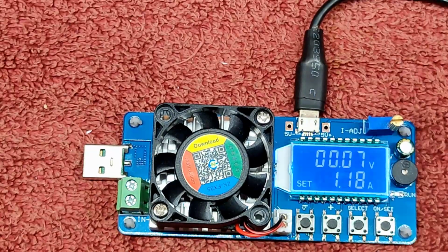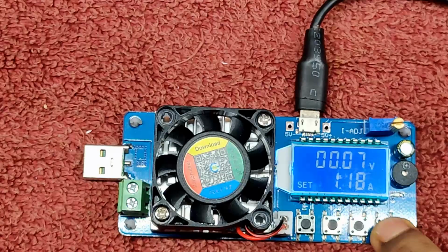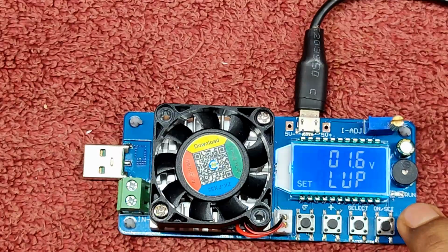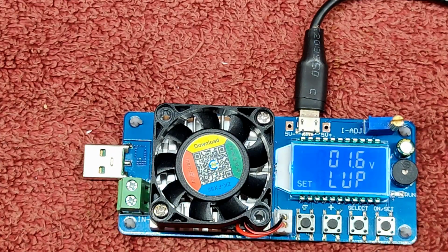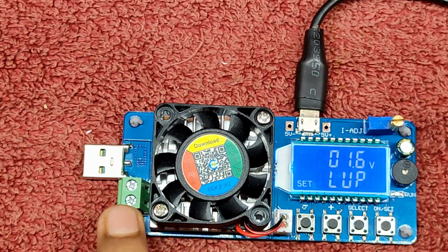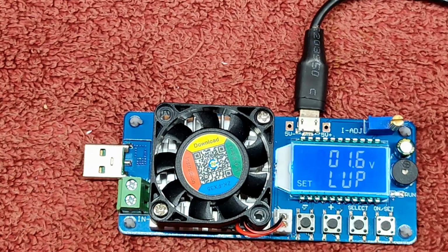To run through the menus, you slightly press the on and set button. If you press it for about 2 seconds, you'll reach the main menu where you can set various parameters. Like here we have LVP, that means low voltage protection. This is currently set at 1.6 volts. That means whenever you put any cell or battery from this USB-A port and run the load, it will measure everything—its capacity, its amperage—and when the battery drains and reaches the 1.6 volt limit, it will beep and alarm you.